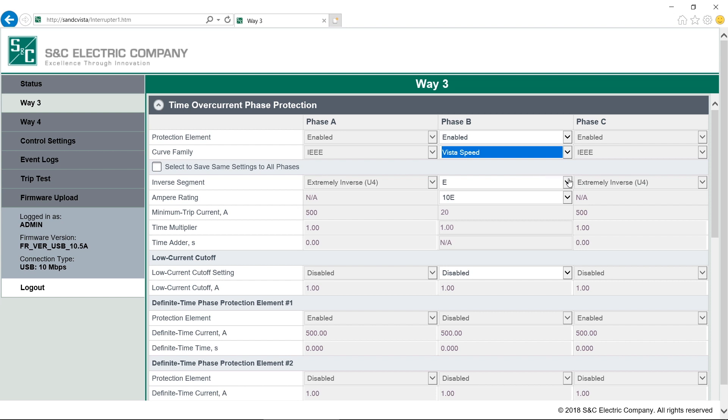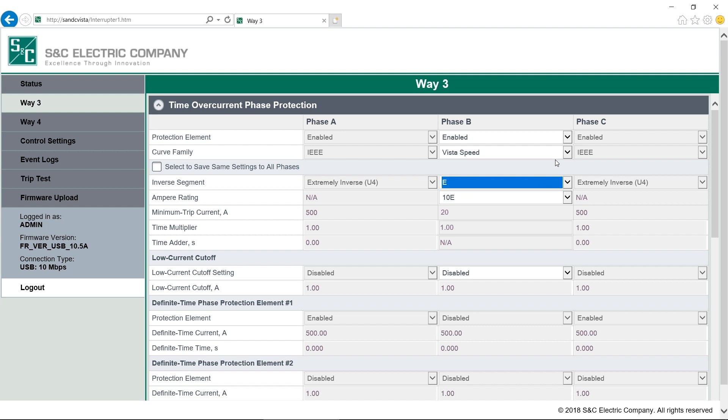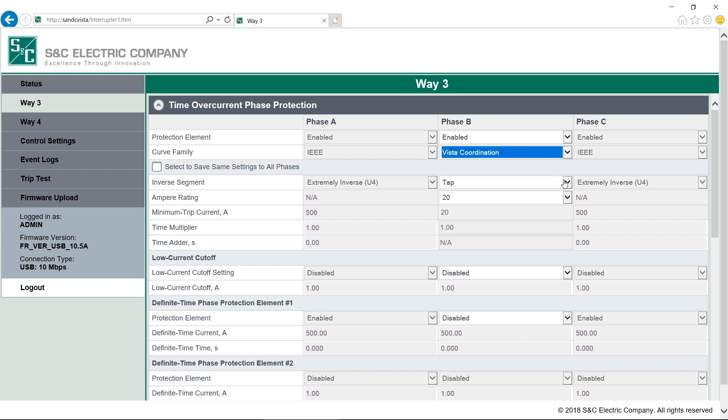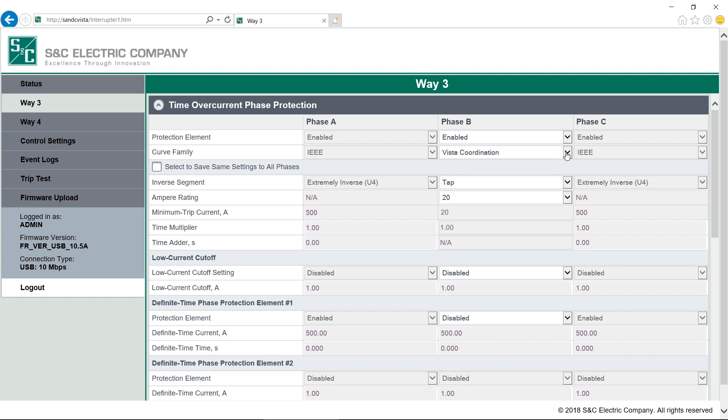Let's start by looking at the two VISTA families. VISTA Speed emulates common fuse curves like E, K and T. VISTA Coordination includes proprietary VISTA tap and main curves. This is for a three-phase fault interrupter. Note that all phases are programmed under Phase B. Phases A and C are grayed out and are not editable. We're currently on VISTA Coordination and we can see which attributes are editable. They will be white, like inverse segment. The attributes that we cannot edit are gray, like time multiplier.